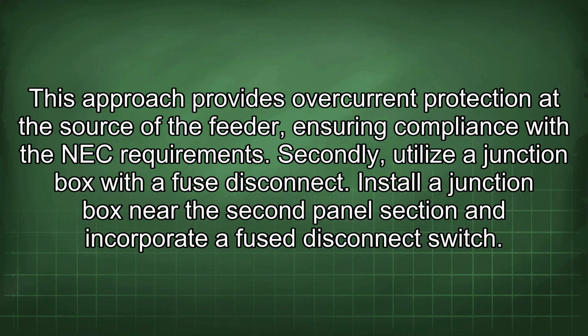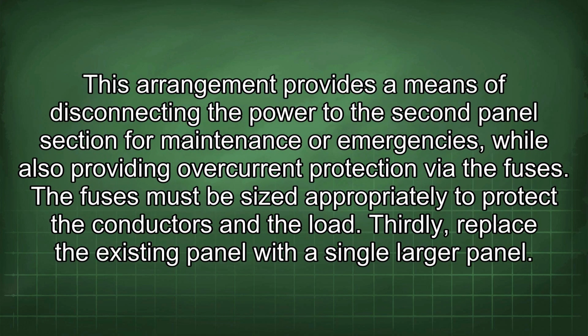Secondly, utilize a junction box with a fuse disconnect. Install a junction box near the second panel section and incorporate a fuse disconnect switch. This arrangement provides a means of disconnecting the power to the second panel section for maintenance or emergencies, while also providing overcurrent protection via the fuses. The fuses must be sized appropriately to protect the conductors and the load.